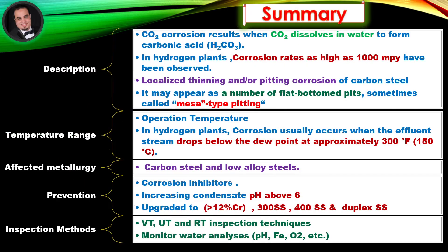Summary — Description: CO2 corrosion results when CO2 dissolves in water to form carbonic acid. In hydrogen plants, corrosion rates as high as 1000 mils per year have been observed. Localized thinning and/or pitting corrosion of carbon steel may appear as flat-bottomed pits, sometimes called Mesa-type pitting. In hydrogen plants, corrosion usually occurs when the effluent stream drops below the dew point at approximately 300°F.